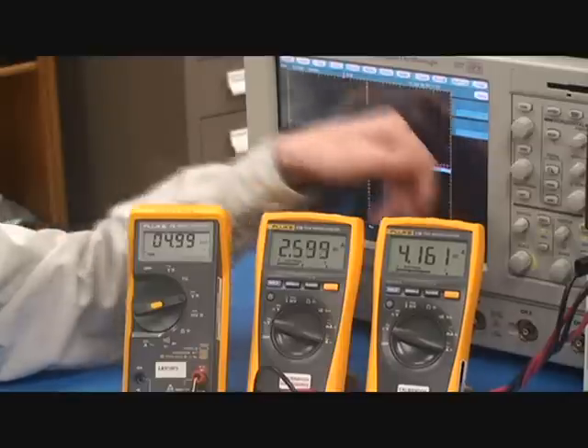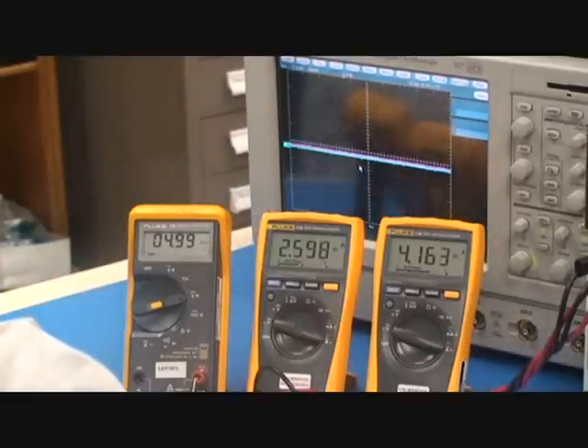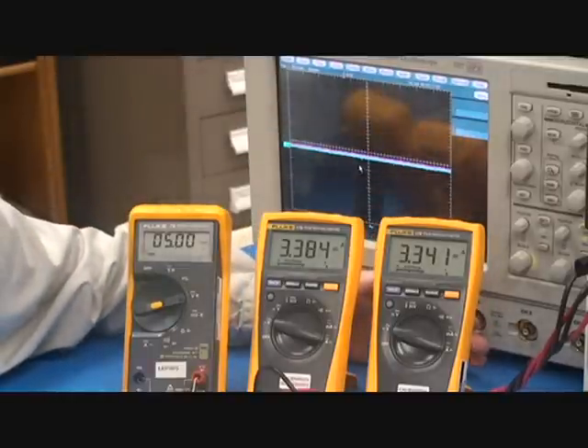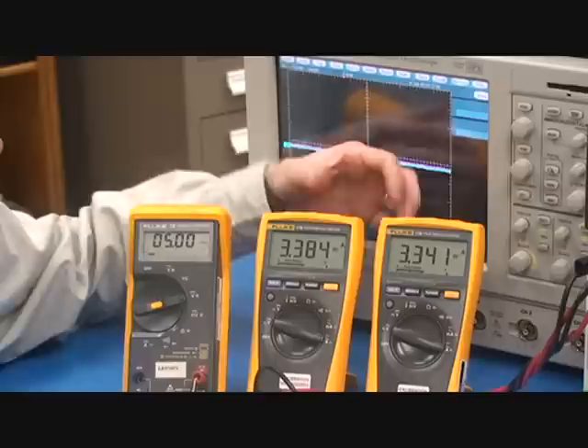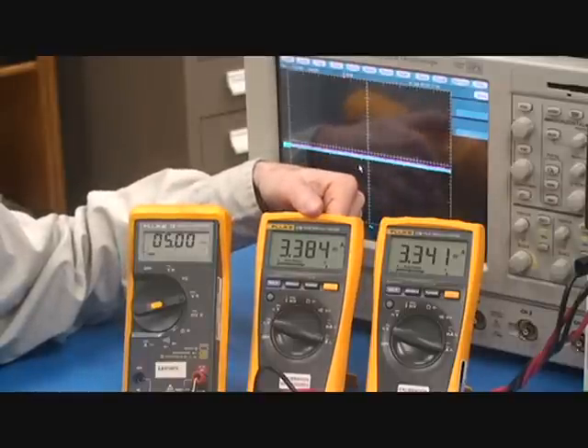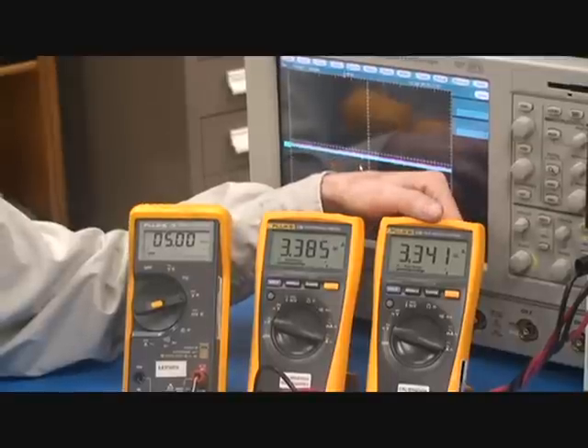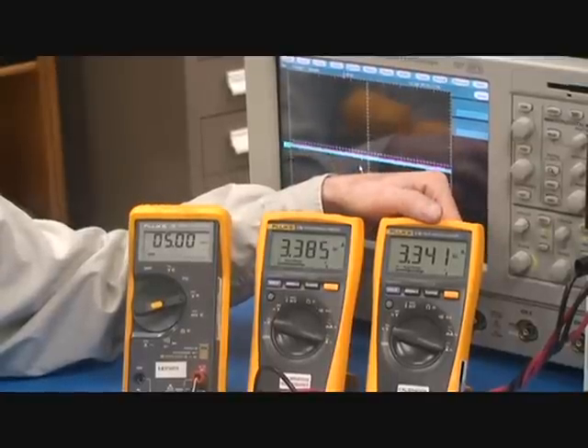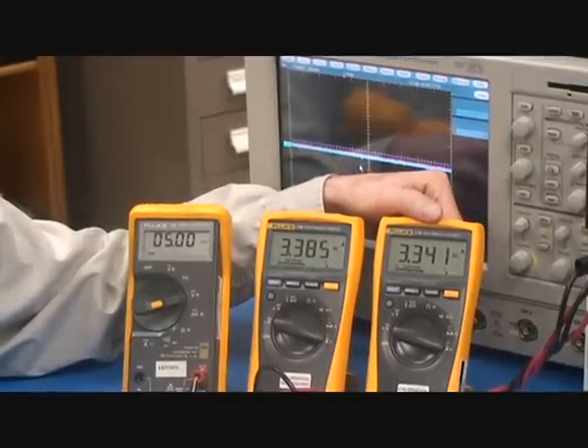Now I will connect the current share. With the current share function connected, you can see the first DVFL now draws 3.3 amps, and the second DVFL also draws 3.3 amps. So they split the load equally.